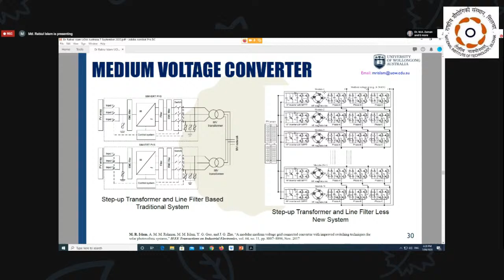So we can think about how to simplify the network. Maybe this is the technology that we can go with. Here you see a technique similar to the one used for the wind power generation system, which can be used to interconnect a solar PV farm to the medium voltage grid without using those heavy and bulky step-up transformers and line filters. We used a high frequency magnetic link. High frequency magnetic links are very small in size, right? It is just for isolation and to produce multiple sources from a single source. No step up here.